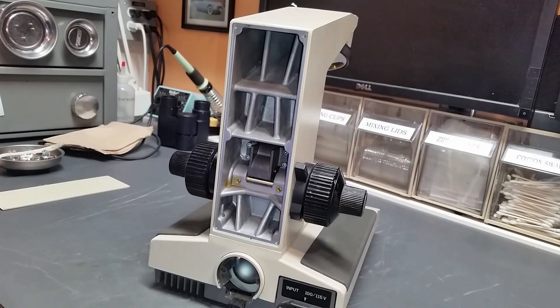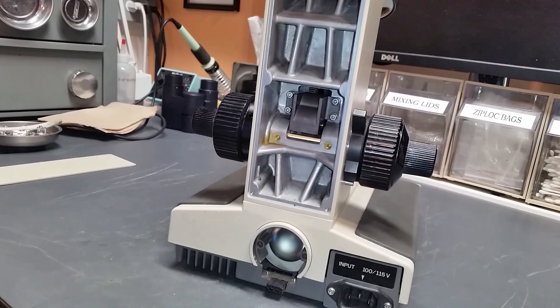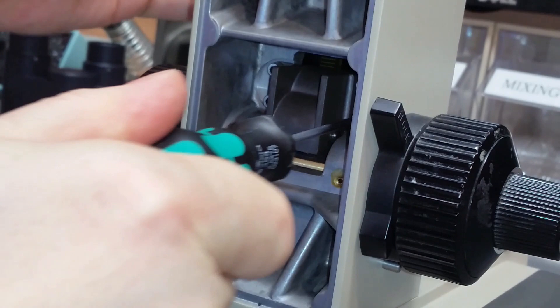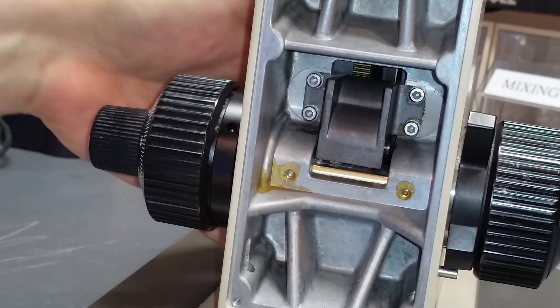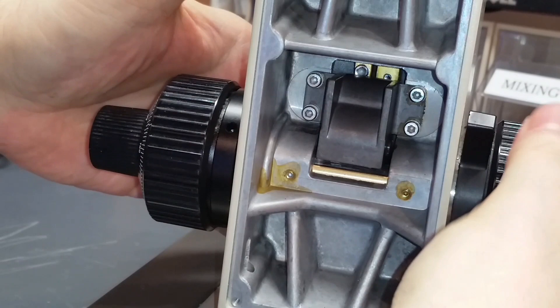Okay, now that the back is off, let's rearrange the camera a little bit so hopefully you can see inside there. But I'm just going to reach in here, and I'm going to loosen up these four hex screws holding the gearbox in place. Okay, they're all loose now. What I'm going to do is I'm going to hold the focus block, or actually I'm just going to rotate it down since it does move. Then I don't have to worry about it dropping when I pull the gearbox out. So now I'm going to loosen up these screws and totally remove all four of them.